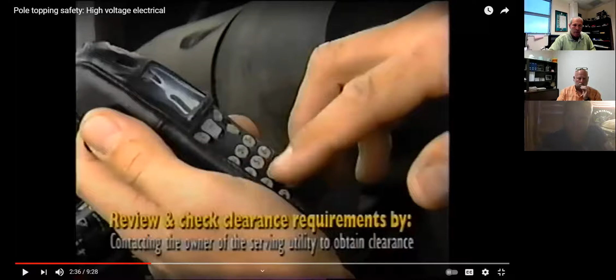I can chime in on this also. You're not going to get a line clearance to chunk a pole out anymore. That's way too much work, and getting a line clearance means customers without power. You are going to get permits on the line to do your work, but actually de-energizing the line to chunk a pole out, which should take no more than an hour, isn't done anymore because of the amount of work involved and the disruption to customers. So you're going to take more time to do it energized than you would with a line clearance.